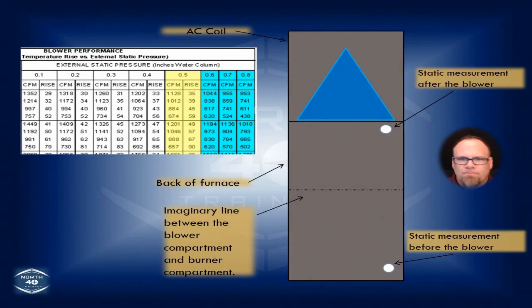So, checking the airflow. And here we are talking about air conditioning systems and checking the airflow. And we hear terms like external static pressure, or ESP, thrown around all the time. So what does that actually mean? Well, ESP, the external static pressure, basically static is a fancy word for resistance, right? So we're looking for resistance external to that furnace. So everything that is before the furnace, including the filter and all the ductwork, and everything that's after the furnace, including the coil and all the ductwork, are all included in this measurement.